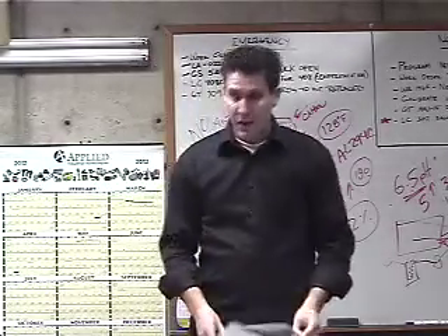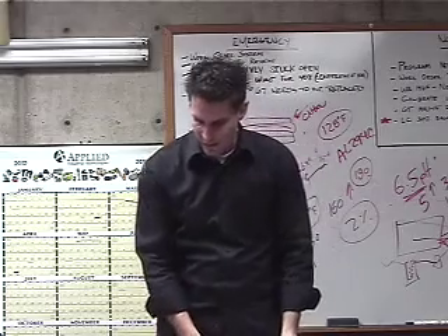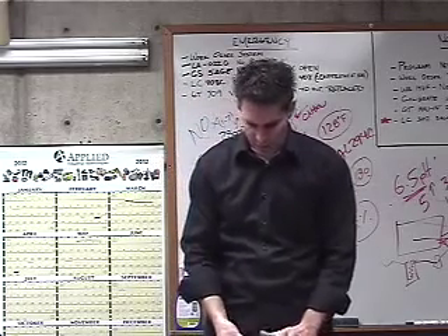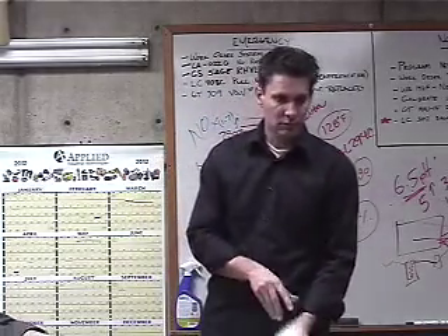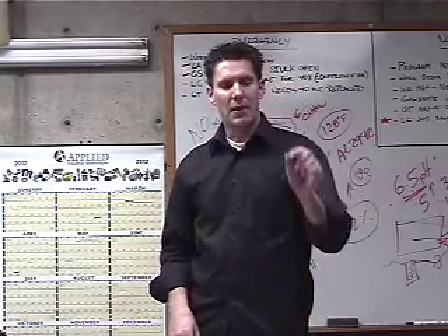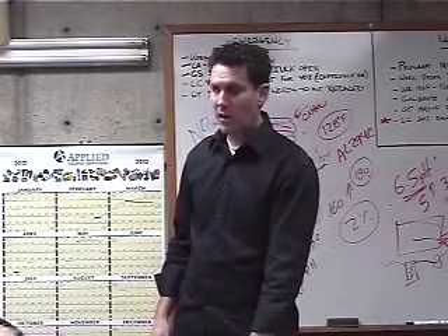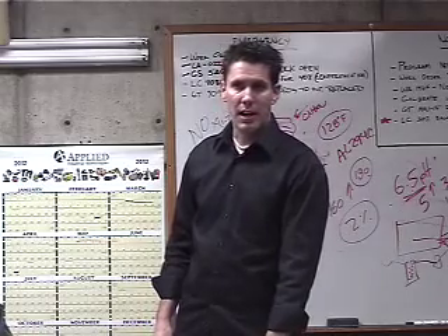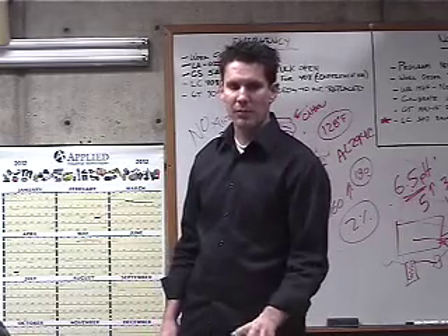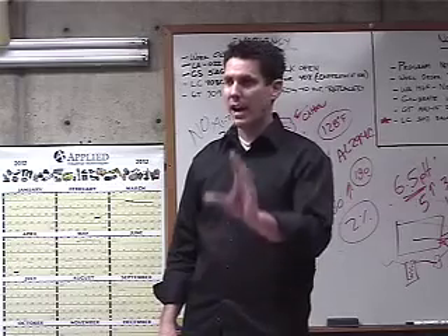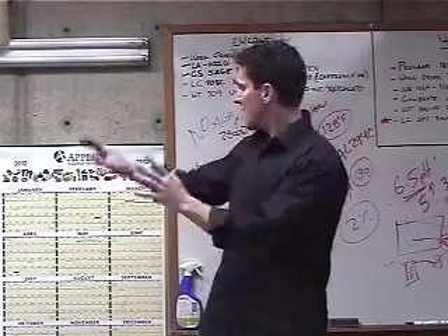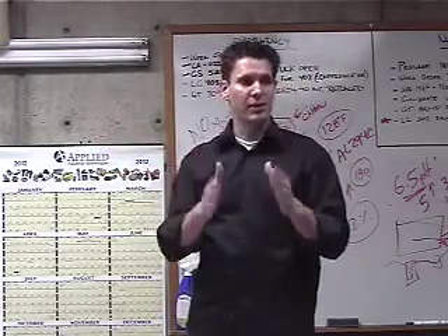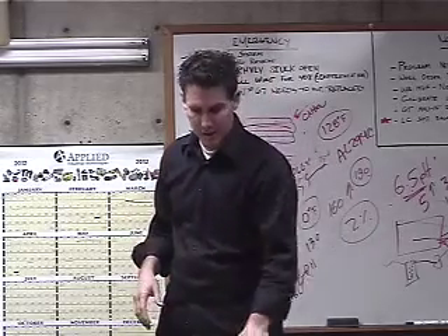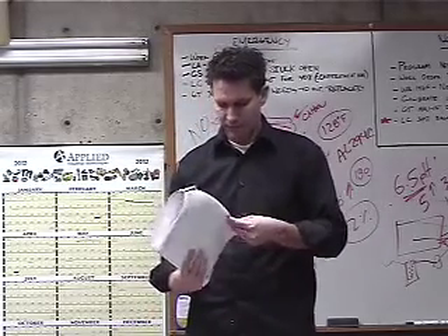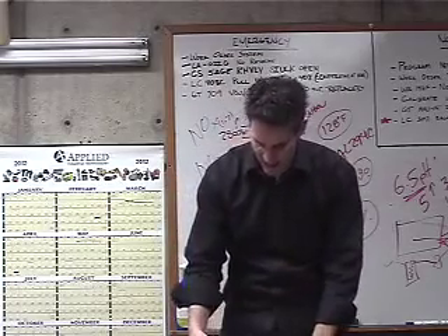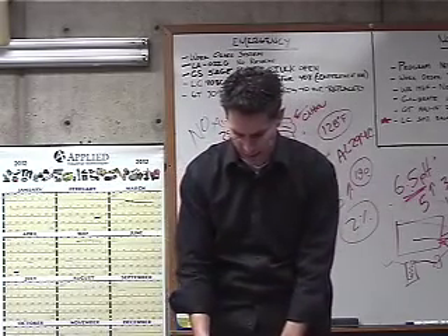And then as far as the maintenance, let's go over the maintenance here. Turn to 4.2. Your boilers came with an O&M manual. Each boiler had one. I would copy that, and pin the next section I'm going to go over on the side of your boiler or up on a wall, somewhere where you know this is what I've got to do and this is when I've got to do it. If you go to 4.2, it breaks it down by day, by week, by month, by every year.